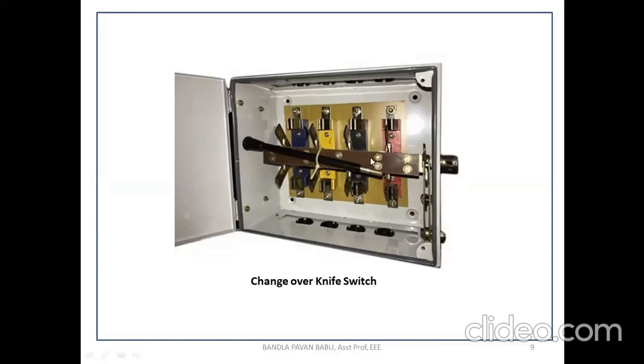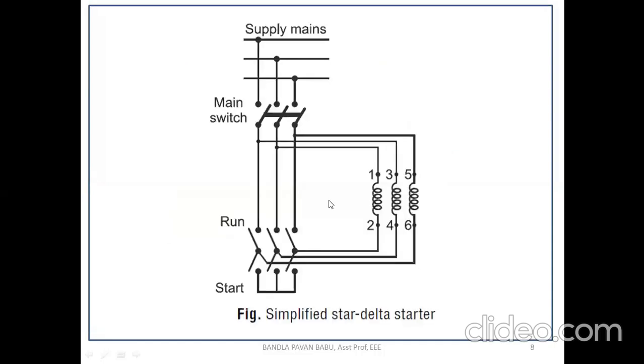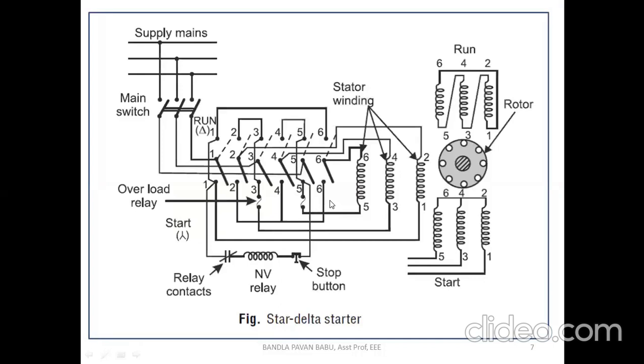If it is in the middle portion, it means there is no connection. You can see here it appears to be a knife, and you can see the tappings here: R, Y, B, neutral. So there will be supply here, and here also. Sorry, this is the breaking point; these are the breaking points. This gives one set of connections and this gives another set of connections, and we tap it based upon our requirement. So this is nothing but a changeover knife switch.